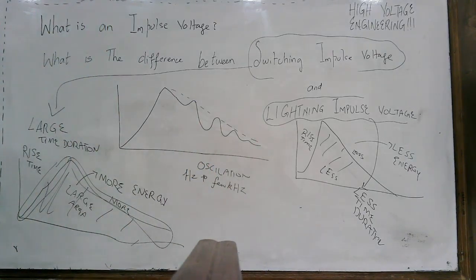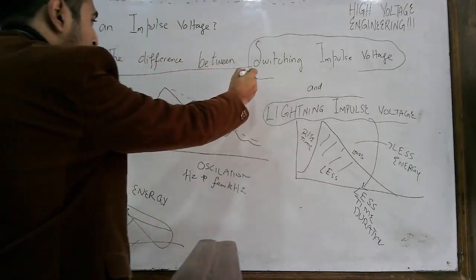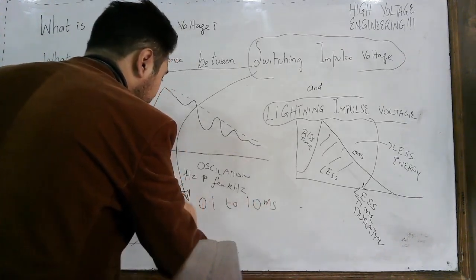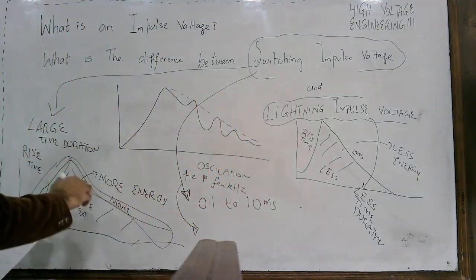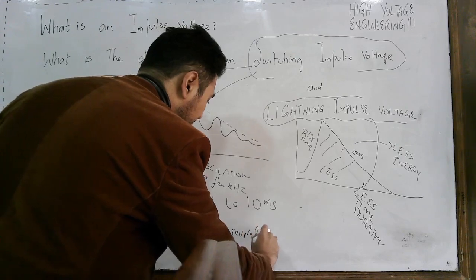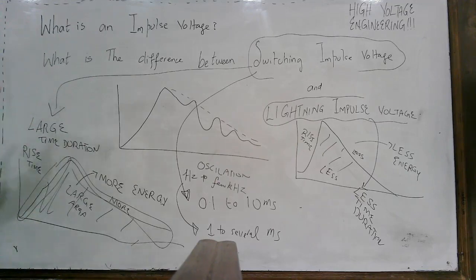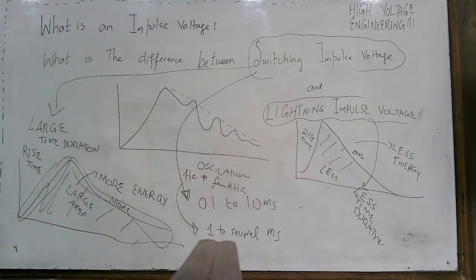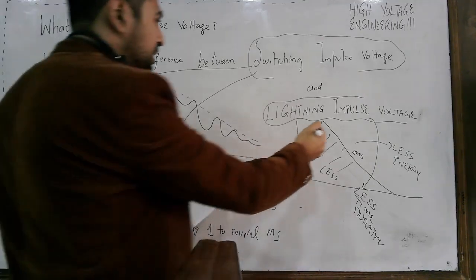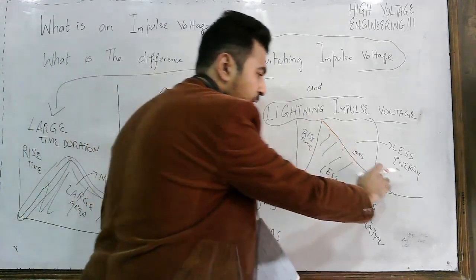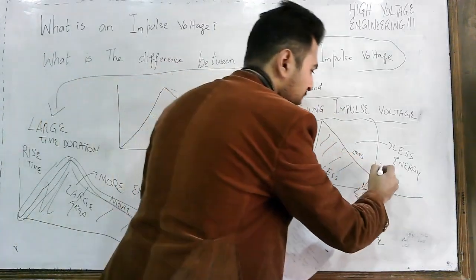One more important parameter is the wave front time. For a switching impulse waveform, the wave front time is typically around 0.1 to 10 milliseconds, and the wave tail time is around 1 to several milliseconds. So the switching impulse voltage has a high wave front time as well as a greater wave tail time. On the other hand, for the lightning impulse voltage, the rise time is around 1 to 2 microseconds only, and the wave tail time is up to 50 microseconds.